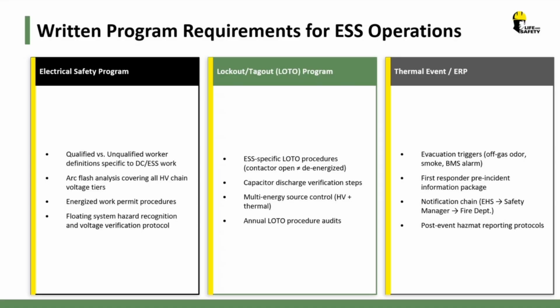That was a deficiency I found. Capacitors maintain their energy even after the power is off. Discharging requires a bleed-down resistor or probe, some type of circuitry. Typical VFDs and other electronic equipment with capacitors and battery management systems have a self-discharge circuit built in, so killing the disconnect bleeds them down automatically. Some capacitors, like those used in power factor correction or phase banks, don't have that bleed-down circuitry, so they maintain energy even after power is off. It's important to identify and label those clearly, using appropriate signal words—danger, warning, caution—for the hazard at play.